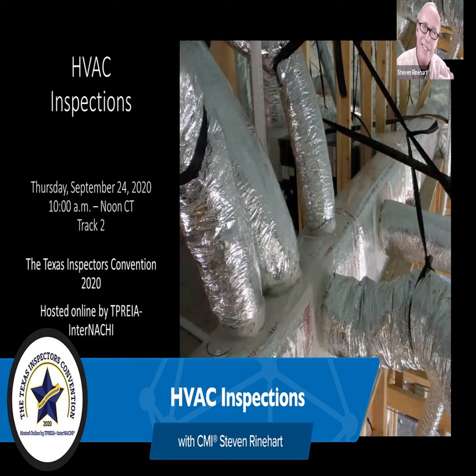The pads, if they get out of level, is there a degree? I haven't read one, but everybody's got a smartphone with a bubble app on it, I'll put it up there. And if it's a few degrees, if it just looks, when I look down the side of the house, it's out of level. Remember the refrigerant in the compressor is where the lubricating oil is. And if it's leaning to one side, it's kind of like driving your truck prolonged on a slope, all the engine oil goes to one side. Not a good idea. That's why they want them level.